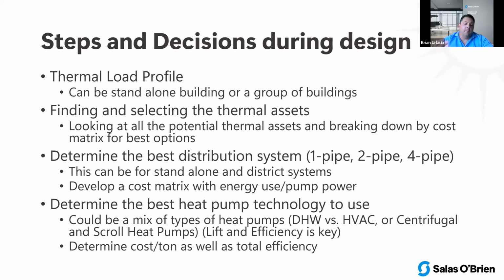Then we look at heat pump technology. What do we use, what's best? It really depends on the project, the site, the building, or the campus. If it's a central plant, are we looking at chillers, and what type, considering the lift and the outlet and load temperatures we need on the hot water side? If we're including domestic hot water, that's year round, so do we want one heat pump delivering 130 degrees even in summer, or could we reduce that to maybe 95 for reheat only? Maybe we need a couple different types of heat pumps married together. If it's a single building, are we doing domestic hot water, using distributed heat pumps for HVAC? Those have different efficiencies because of the load and source temperatures they work under.